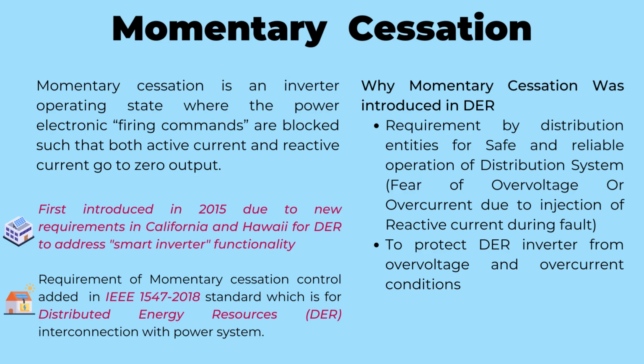Let's rewind to 2015. When new requirements emerged in California and Hawaii to enforce smart inverter functionality within distributed energy resources, DER, this led to the inclusion of momentary cessation control in the IEEE 1547-2018 standard, specifically designed for the interconnection of distributed energy resources with the power system. So, what drove the introduction of momentary cessation in distributed energy resources? Distribution entities sought to ensure the safe and reliable operation of their distribution systems, driven by the fear of overvoltage or overcurrent caused by the injection of reactive current during faults. This measure was implemented to shield distributed energy resources inverters from such precarious conditions, safeguarding their longevity and performance.